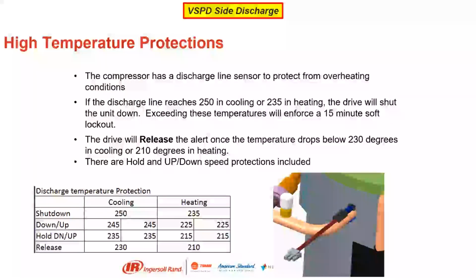High temperature protections. Discharge temperature: if that compressor in heating mode goes above 235, it's going to have a shutdown. It releases or resets back at 210. So if we're not reading correctly and it's reading higher than 235, we're going to get an alert, which in some cases does happen, and go into soft lockout. So we want to verify: if we take a pipe clamp here and it's only 150, which is a normal reading, and this is reading 250, we got a bad discharge temperature sensor. And then we can verify it with volts DC, what it's actually reading.